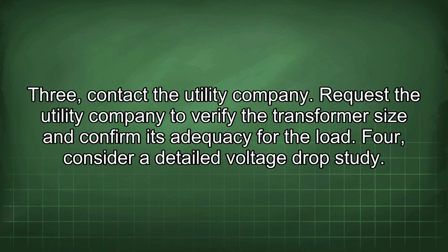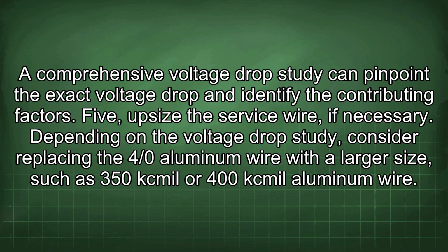3. Contact the utility company. Request the utility company to verify the transformer size and confirm its adequacy for the load. 4. Consider a detailed voltage drop study. A comprehensive voltage drop study can pinpoint the exact voltage drop and identify the contributing factors. 5. Upsize the service wire, if necessary. Depending on the voltage drop study, consider replacing the 4/0 aluminum wire with a larger size, such as 350 kcmil or 400 kcmil aluminum wire.